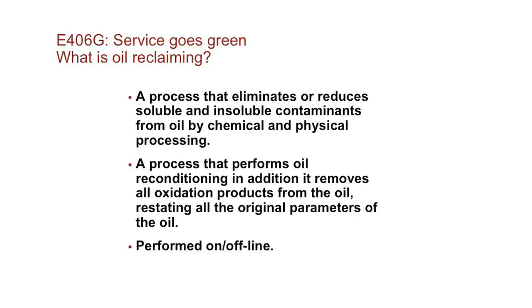The process, we recondition the oil. As I said, we remove the oxidation that has occurred over time. In that process, we also remove the oxidation inhibitor or stability. So we have to re-add the oxidation inhibitor back to the oil after the process has been performed. Two options here: we can perform this process online energized or offline de-energized.